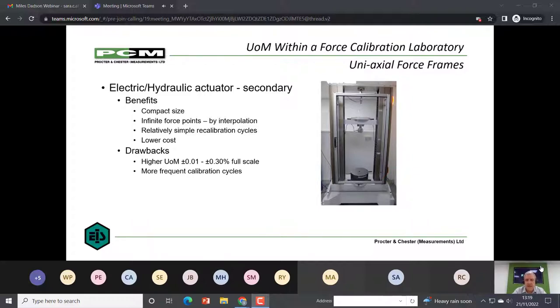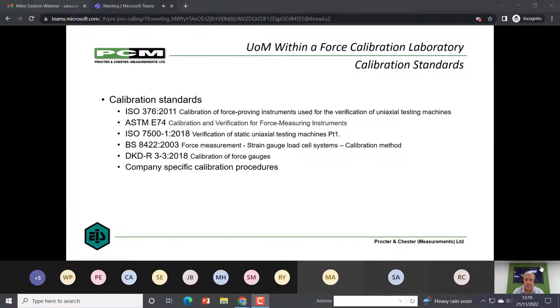The drawback of this is that, because you're relying on a primary calibration source, the uncertainties tend to be a bit higher. That means you tend to calibrate more industrial devices rather than what National Physical Laboratory and other national bodies can do. There are also more frequent calibration cycles because you've got more equipment within it.